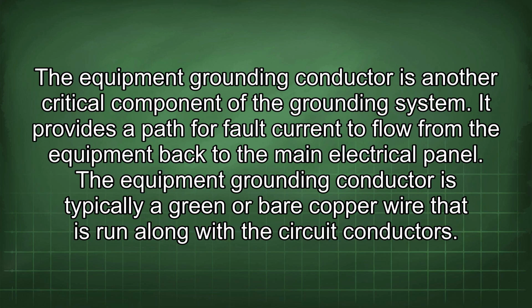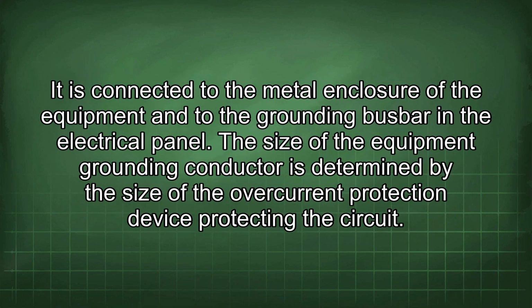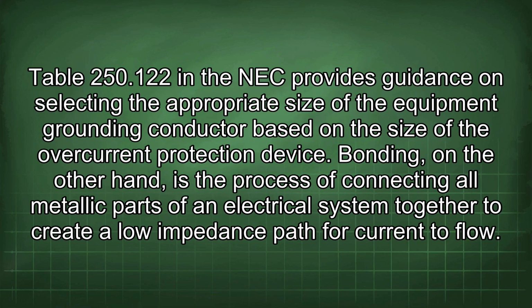The equipment grounding conductor is another critical component of the grounding system. It provides a path for fault current to flow from the equipment back to the main electrical panel. The equipment grounding conductor is typically a green or bare copper wire that is run along with the circuit conductors. It is connected to the metal enclosure of the equipment and to the grounding busbar in the electrical panel. The size of the equipment grounding conductor is determined by the size of the overcurrent protection device protecting the circuit. Table 250.122 in the NEC provides guidance on selecting the appropriate size of the equipment grounding conductor based on the size of the overcurrent protection device.